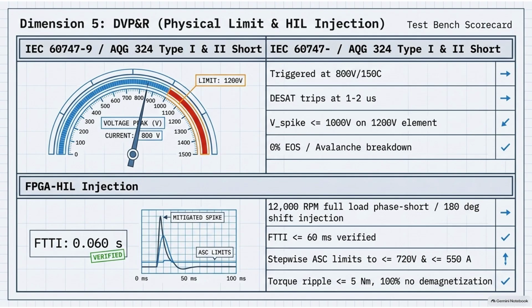Type 1 testing is a hard short applied before the system is even powered on. Type 2 testing is far worse. They get the inverter running at full load, switching at high frequency, and then maliciously slam a dead short across the output. They hit it with a sledgehammer. And the benchmark to pass is absolute survival. The UCC5880-Q1 gate driver must detect the fault, initiate the two-stage turnoff, and kill the current in under 2 microseconds. The resulting avalanche voltage spike must be choked by the 15 nanohenry busbar and clamped below 1,000 volts. Incredible. And critically, after the fault is cleared, the system must remain fully functional with zero secondary damage.